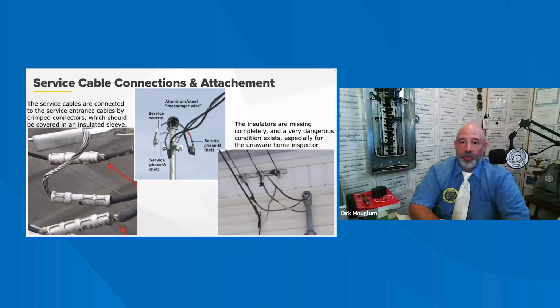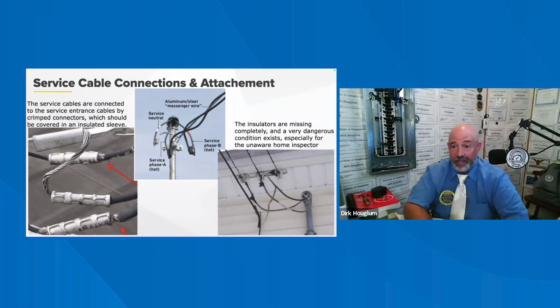Okay. Point of attachment to the building or structure. A typical 3-wire service drop consists of 2 insulated hot conductors wrapped around a bare stranded aluminum wire with an internal steel messenger cable. The bare aluminum wire also serves as a neutral. The middle image above shows the overhead service drop and the weatherhead, including the 2 hots and the 1 bare, stranded service neutral. The neutral, or the grounded conductor, also serves as the main physical connection to the building. The inspector should ensure that the strain relief is not detached or pulled away from the structure. The point of attachment of the service drop conductors to a building or structure must have a clearance above the finished grade of at least 10 feet.